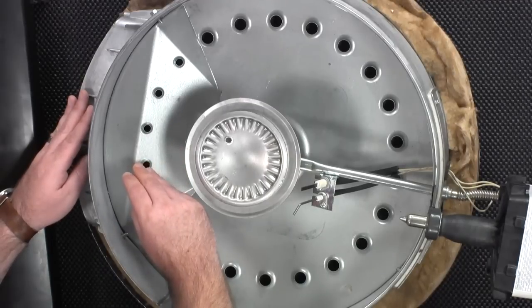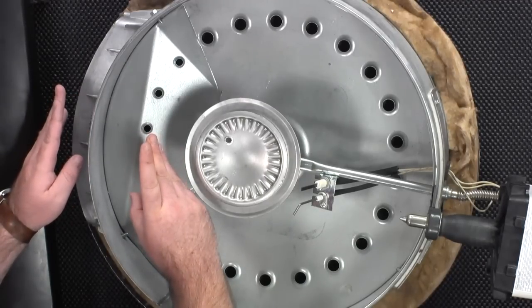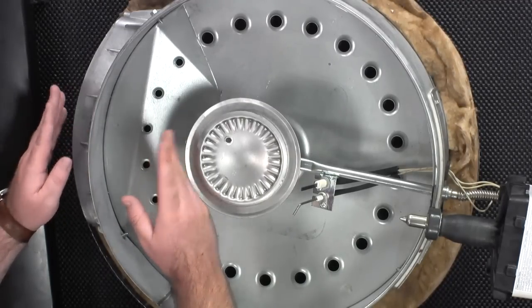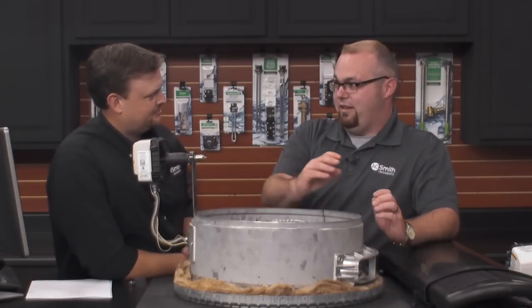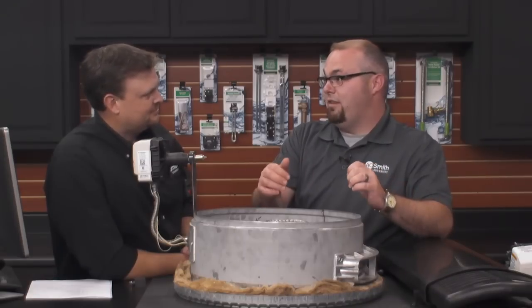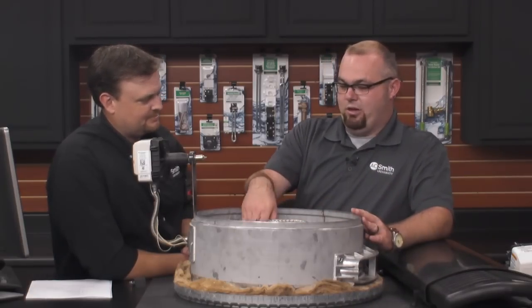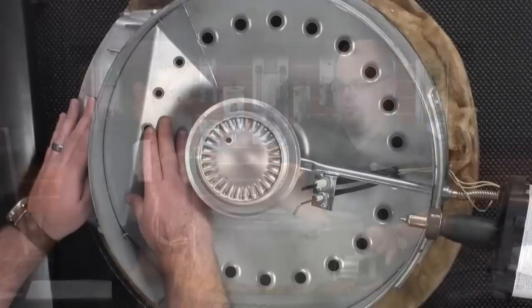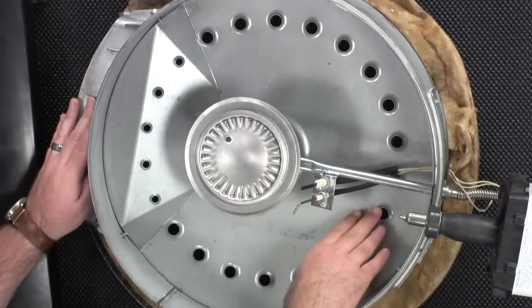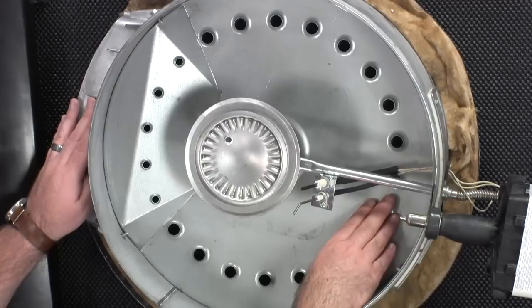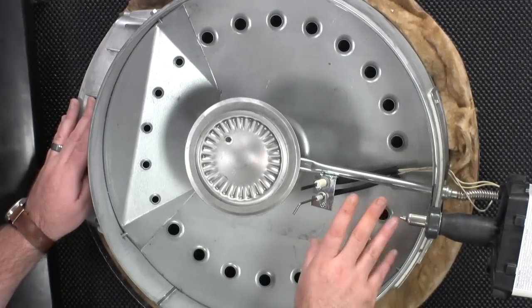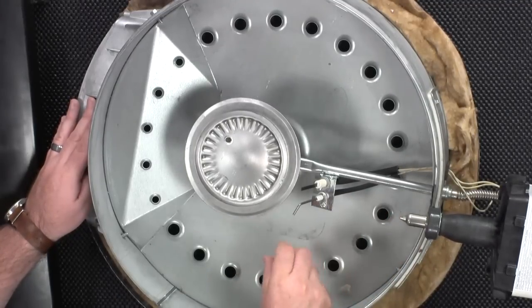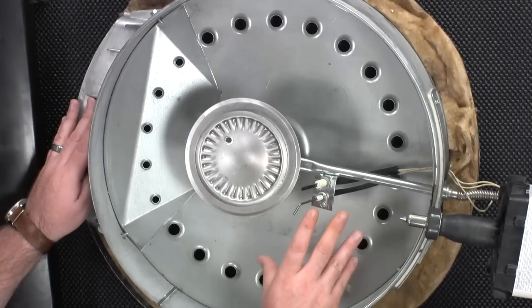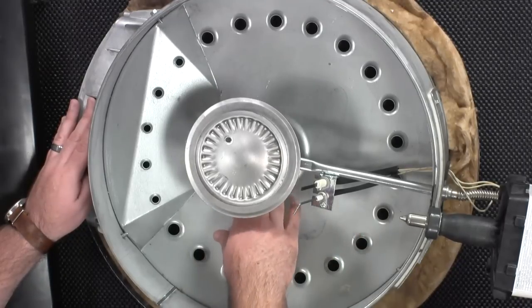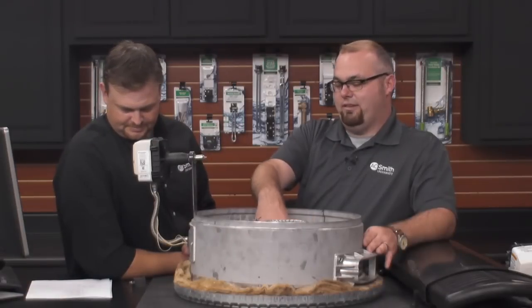Just like with anything that moves air, even the ductwork in your house, the closer the vent is to the main unit, you would have the dampers closed more. The further away, they may be fully open. Same sort of deal right here. The closer we are to our source of combustion air, the smaller the holes. When we get further away from it, the holes get bigger. A lot of this helps with a smoother light off, a nice clean burn, the way it's delivering air. Of course, we have a big hole directly up under the burner that you can't really see.